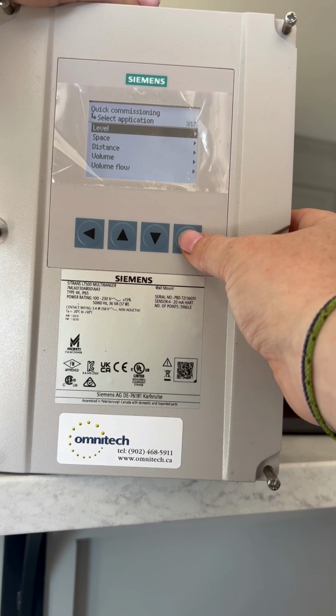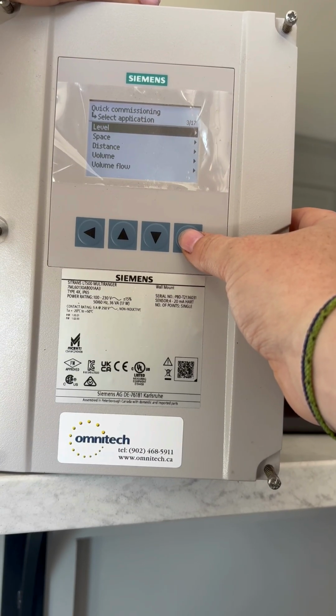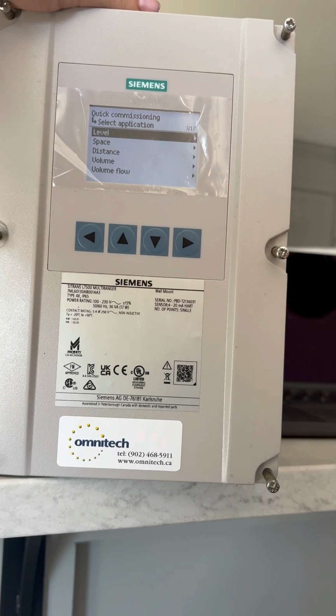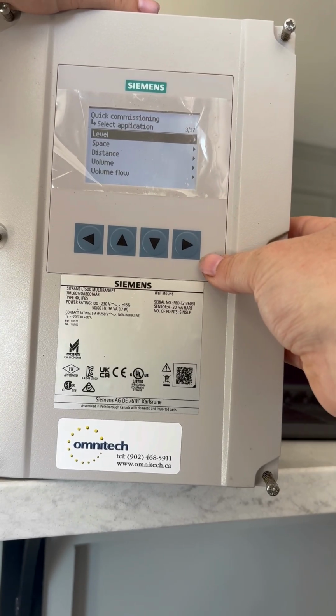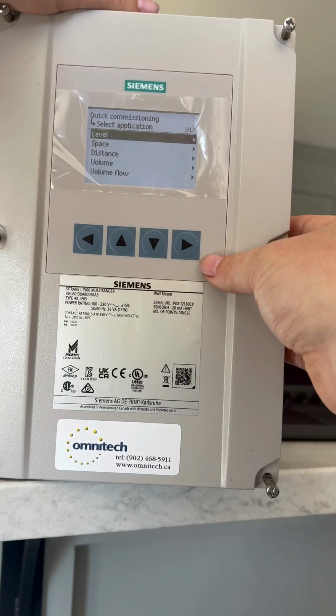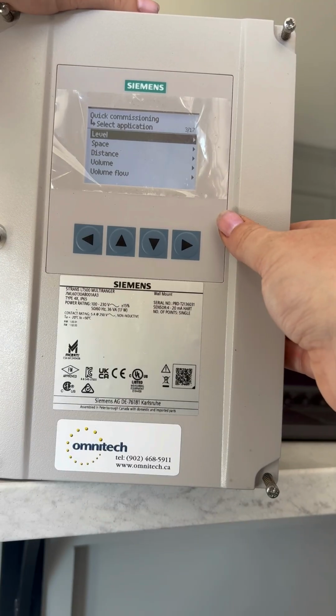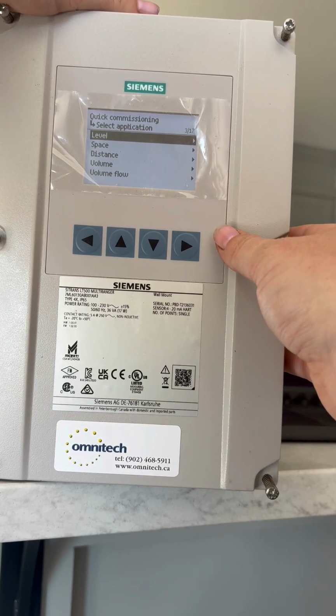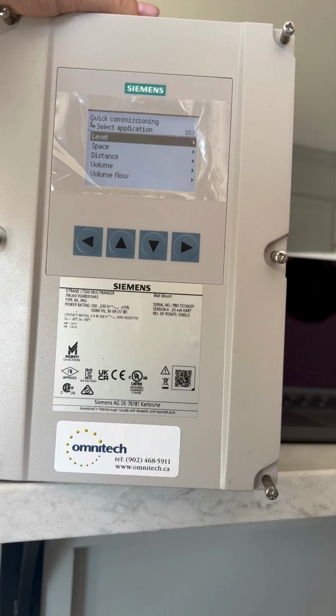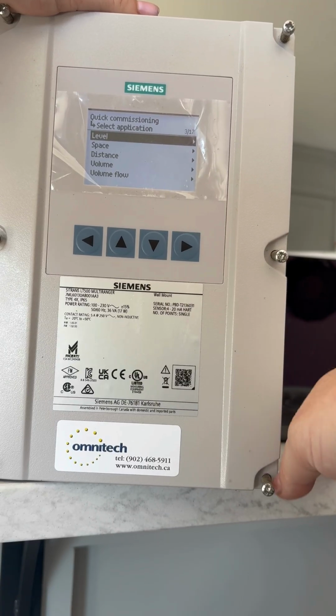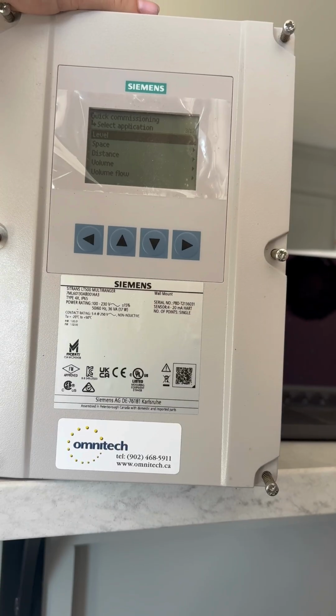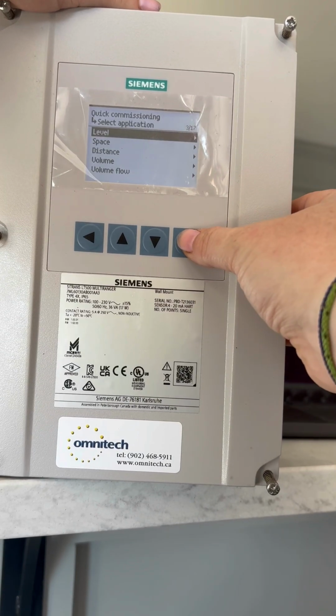For example, when we get this installed, if the actual high level is going to be 11.9 or maybe only 11 feet, maybe we want to scale it so that our relay goes off at 10 instead of 11. Currently 0 to 12 feet is the range, and we're expecting that once it drops a foot, to 11, we want to turn on the solenoid to open the valve for more incoming water.